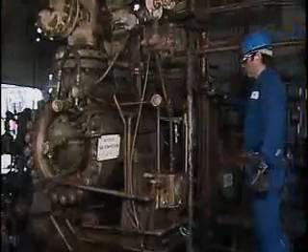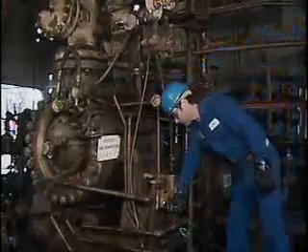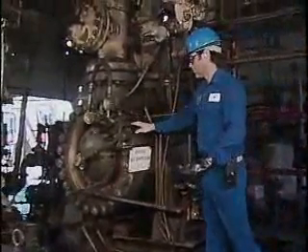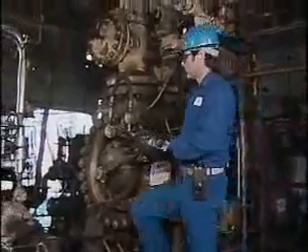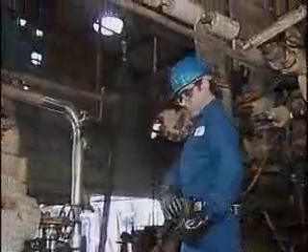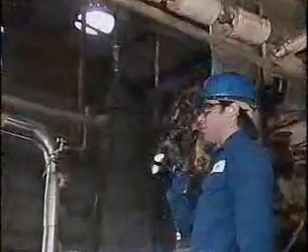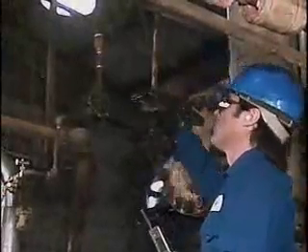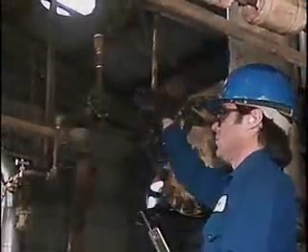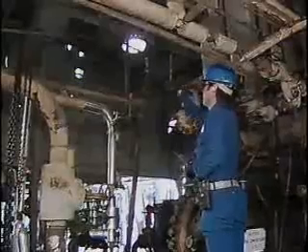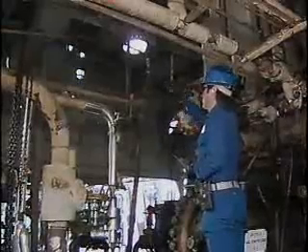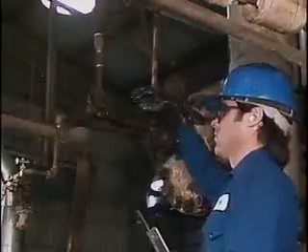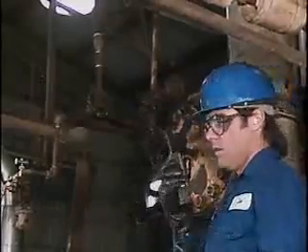In addition to starting and checking the auxiliaries, the operator also checks the compressor to make sure it's ready to be started. He checks the equipment for abnormal conditions, such as loose or missing parts. This compressor is driven by a steam turbine. The compressor handles a flammable gas, so it must be purged with steam or an inert gas, such as nitrogen. The operator does this by opening a manual purge valve. Purging removes air from the compressor and reduces the risk of an explosion or a fire.